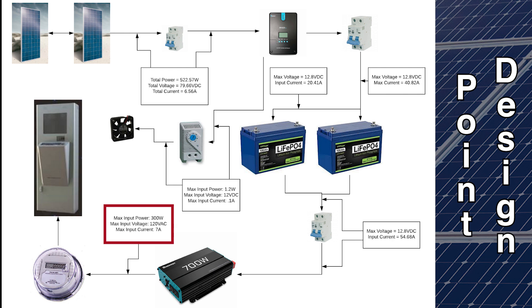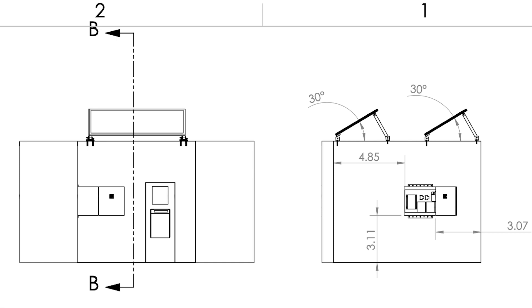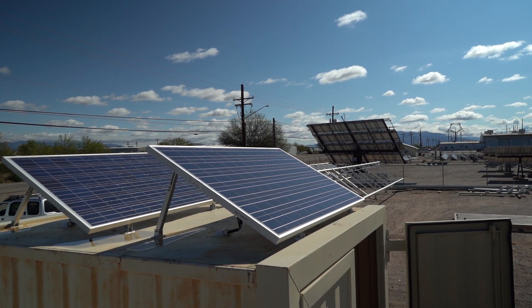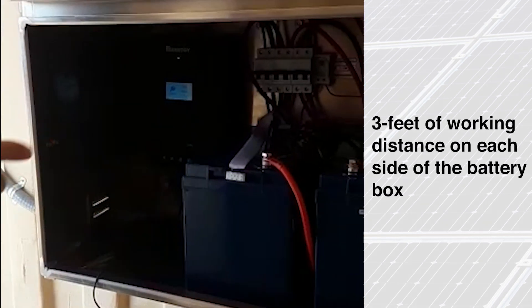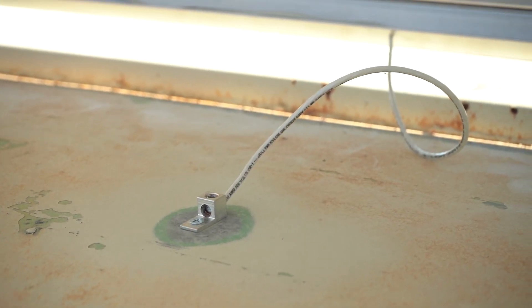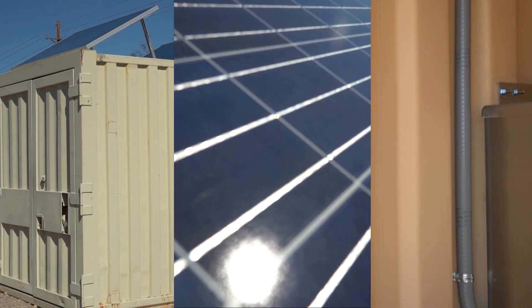there is an overall range of 114 to 125 volts of alternating current. Our physical requirements focus on the dimensions and the setup of the system. Our solar panels are fastened into the roof of the container and therefore are required to fit in less than 8 by 10 feet to account for safe working distance and panel shading. To abide by the National Electric Code or NEC, the remaining MUC components need to fit within the container and still allow a minimum safe working distance of 3 feet on each side to meet our safety requirements. These requirements include having a DC ground fault protection by way of a chassis mounted grounding lug in compliance with the NEC. In all, our requirements make sure that our system focused on meeting and/or exceeding the wishes of our sponsors.